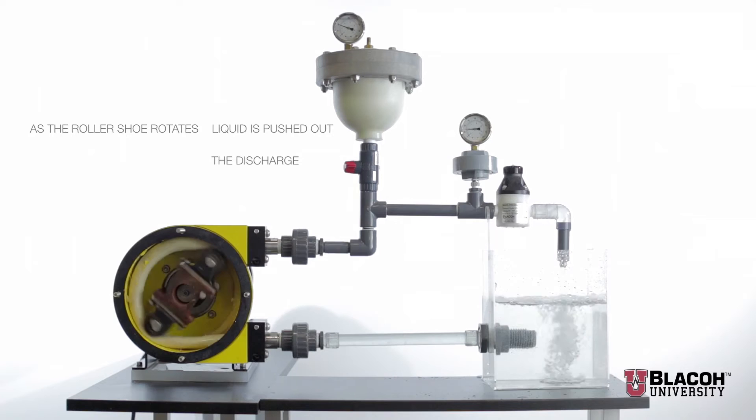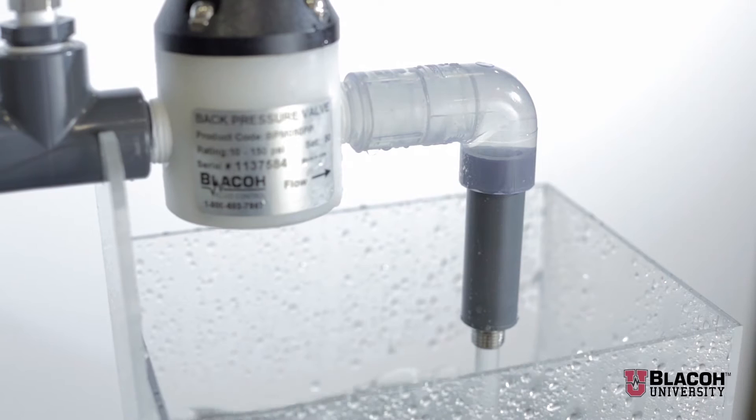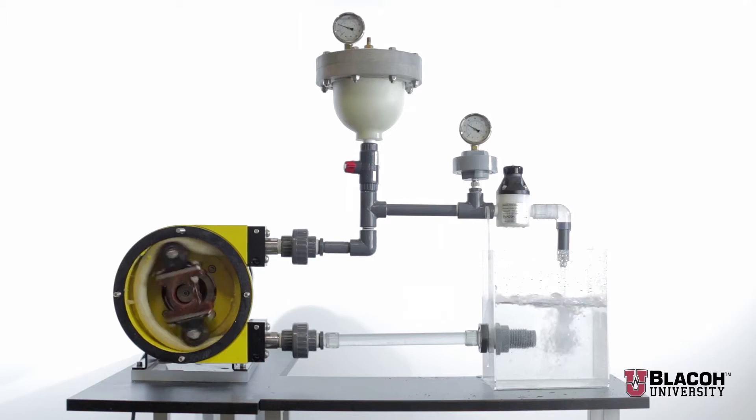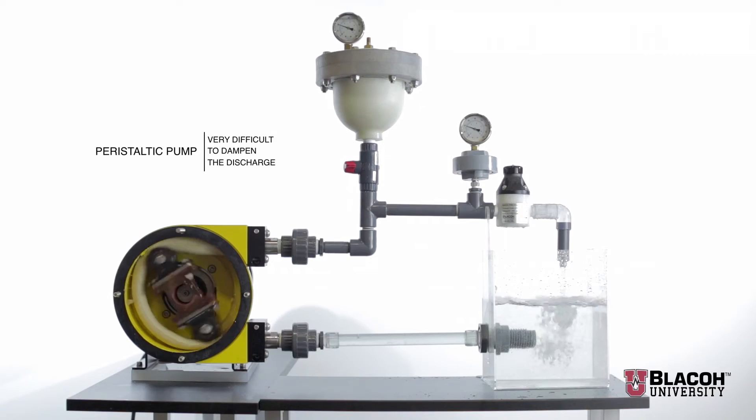When the roller shoe releases the hose after discharge, a momentary void or pocket is created where there is no product. This creates a partial vacuum as some product is actually sucked back to the discharge momentarily. This action, along with the normal pulsing action created by its positive displacement nature, makes the peristaltic pump very difficult to dampen the discharge flow.